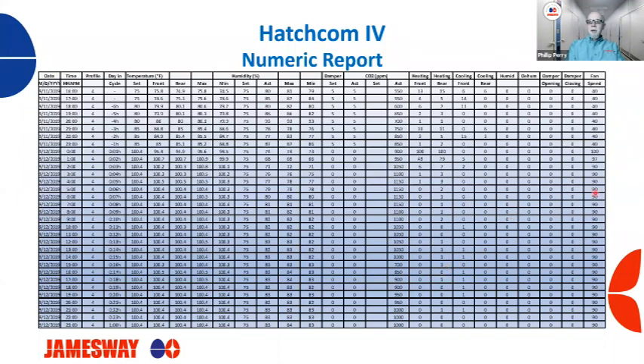If you can see over here, you can see where the fans ramped up to 100%. If you're familiar with that, anytime you have a demand of 100%, this does ramp up to help the machine recover quickly. If we have 100% cooling demand, it would ramp up as well. So if you ever have a fan speed set and it goes up to 100%, that is why. It's because there's a 100% demand either for heating or cooling, and it just tries to help that machine recover as quickly as possible. And then it went back down to 90% for our first day here, until we lower fan speed even more.